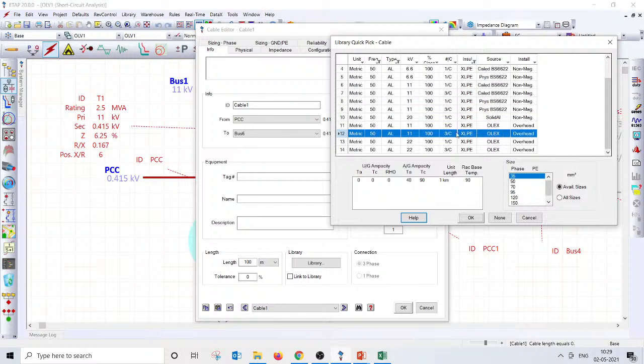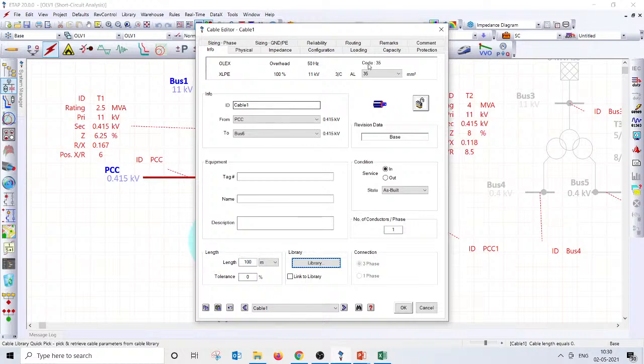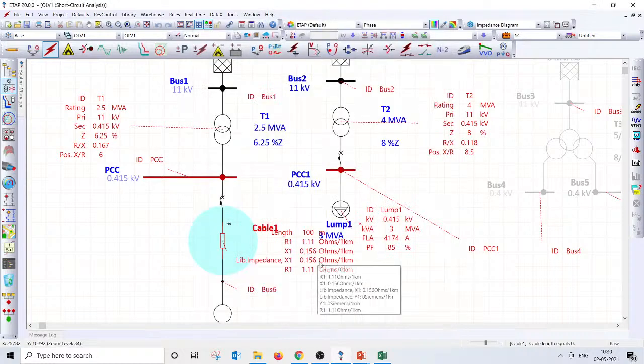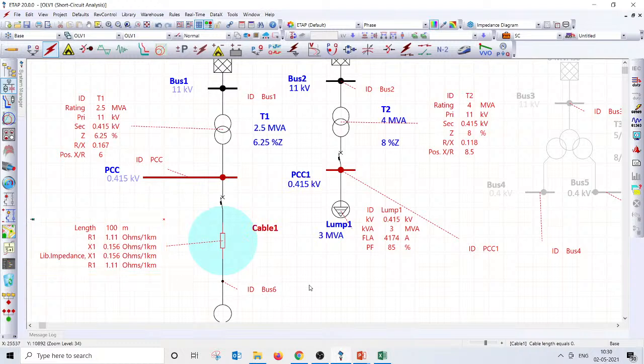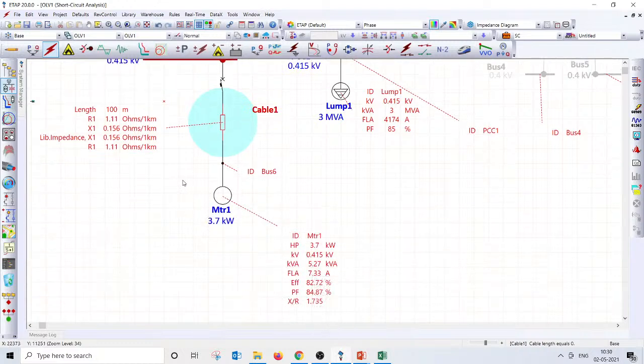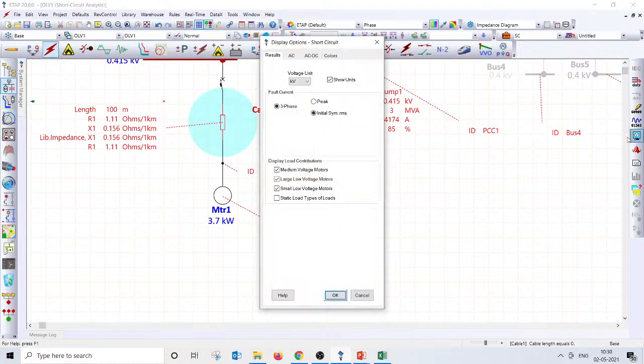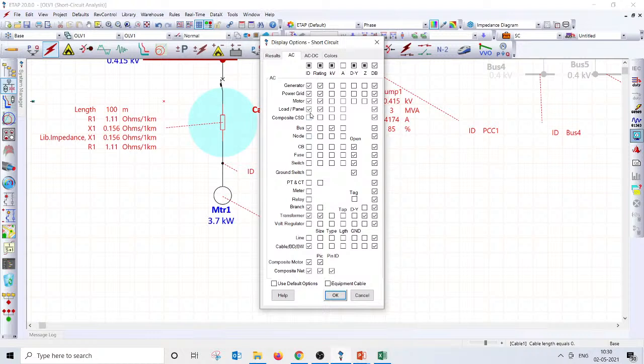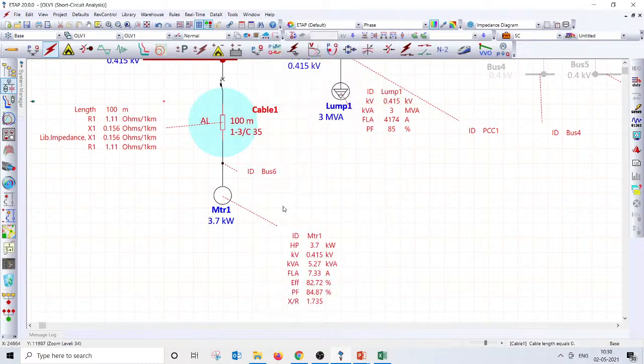Yeah, everywhere this cable size is quite high. Yeah, at least 35 which you have. But even if you take a 35 square cable and try to terminate it in the motor, the people who are at site may understand the difficulty. The size of a 3.7 kilowatt motor itself is small, and the cable terminal box size is too small, and you cannot really terminate this 35 square cable. If you look at the cable which we have selected, cable size, type and length, if I display, yep, 35 square cable which I have selected.